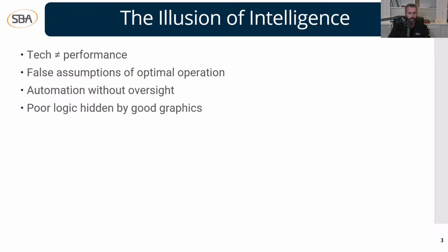Systems left on permanent override can give a false sense of control. Sometimes technicians put them in override just to test things, or to make a problem go away temporarily, and then they forget about it. When you do that, you're locking out all the capability you paid for and invested in your building automation system, and just overriding it to get by—kind of like putting a Band-Aid on it.